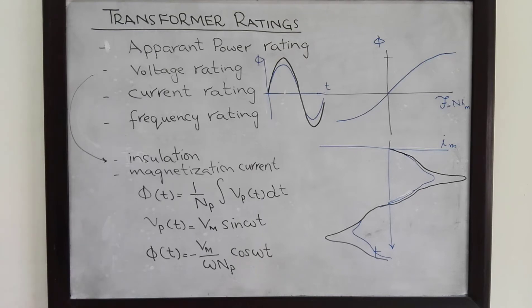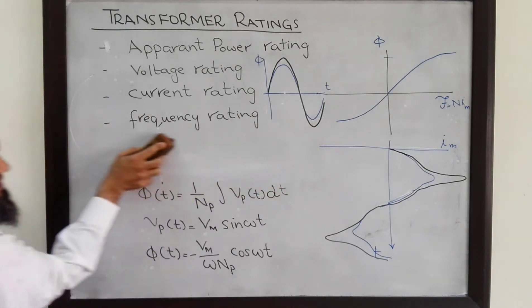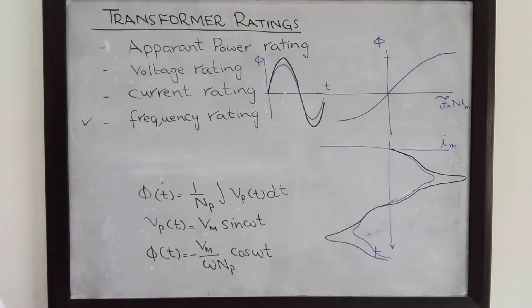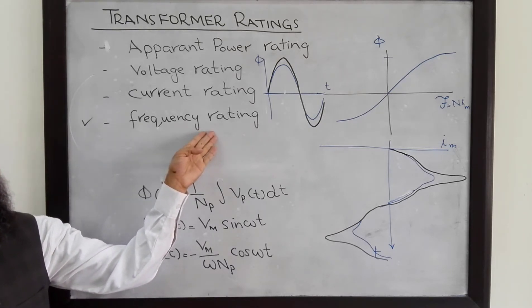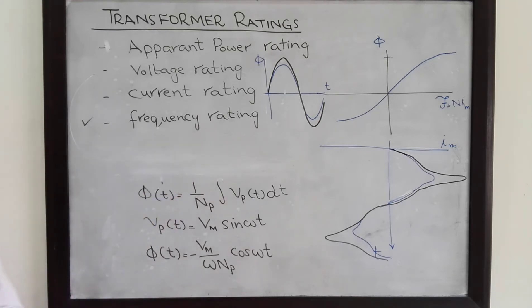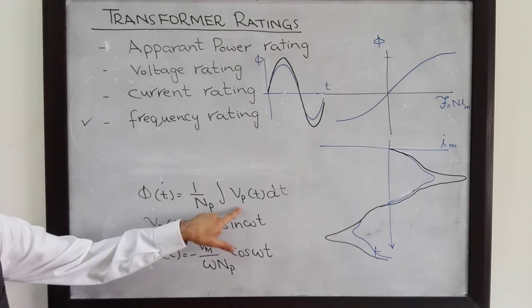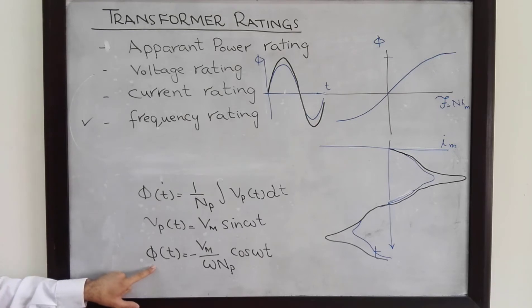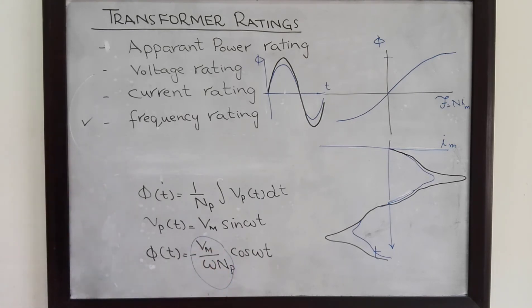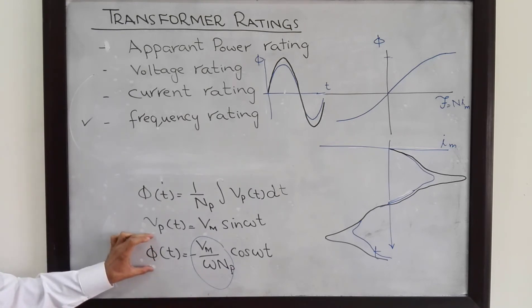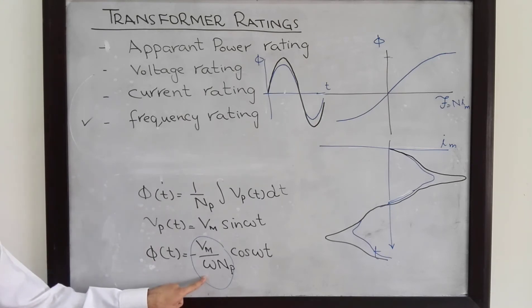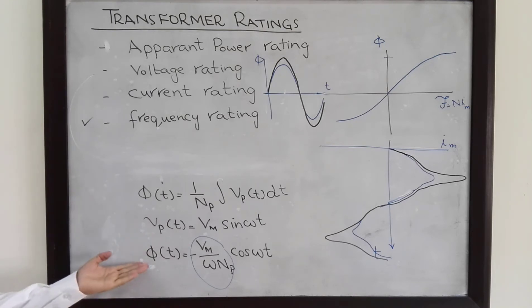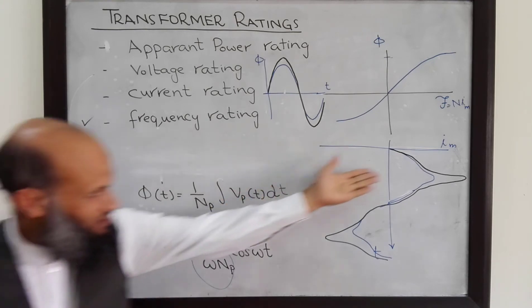The third important rating for a transformer is the frequency. Transformers are designed to work for a particular voltage with a particular frequency. What will happen if the transformer is operated at higher or lower frequencies? That is also apparent from this expression: the voltage on the primary side is related to the flux flowing in the transformer by this relation. For this particular primary voltage, this will be the flux. We can see that by changing the frequency, the maximum value of the flux flowing in the transformer is also changed. Increasing the frequency will result in a decrease in the maximum flux, and decreasing the frequency will result in an increase in the maximum flux. Increase in flux will result in an increase in the magnetization current, as depicted here.